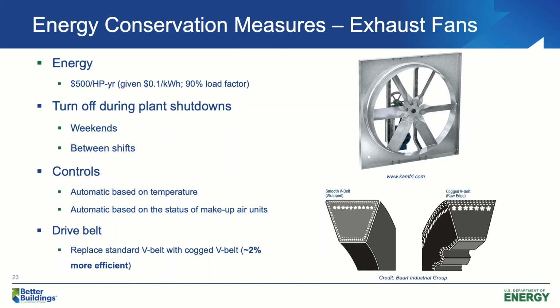Energy conservation measures for exhaust fans. We just talked about this number before, $500 per horsepower per year. This is the annual energy cost for a 1 horsepower motor with 90% load factor and 10 cents per kWh electricity rate. That means if we can reduce operating hours of that 1 horsepower motor by 10%, we can save $50 per year. So the main idea for exhaust fans is to reduce operating hours. Can we turn off our exhaust fans during plant shutdowns for both weekends and off-shift shutdowns? Can we change the controls from manual controls to automatic controls, either based on temperature or the status of makeup air units?